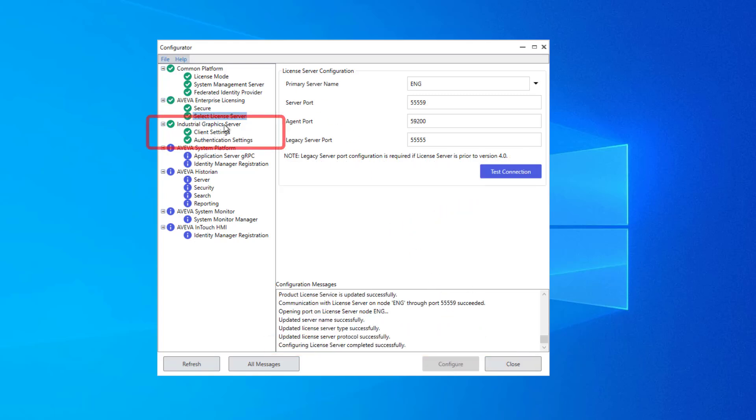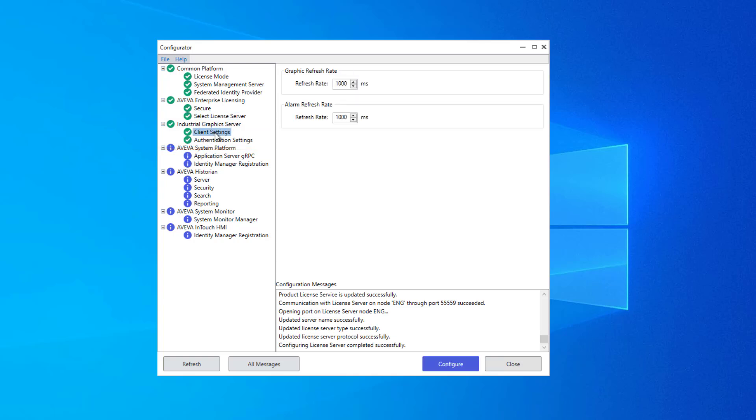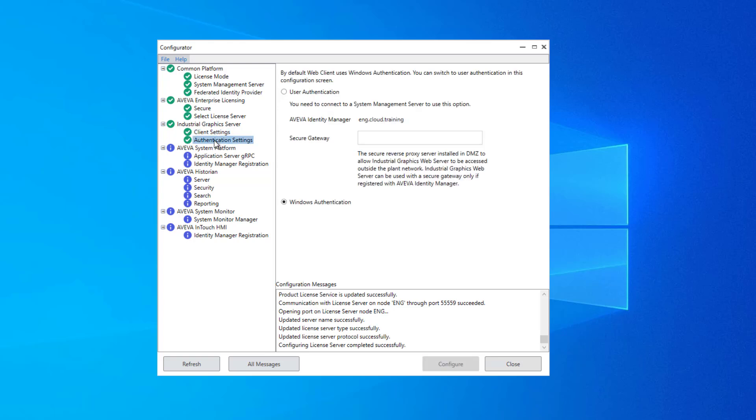The next group, Industrial Graphics Server, is InTouch specific. Though it's already configured, I will make a mention here that Client Settings relates to the Web Client tool. It is basically the rate at which animations are refreshed and alarm information is updated, and these can be adjusted here in milliseconds. And then we have the authentication settings. This is again used by Web Client to establish user authentication. It is using Windows authentication.